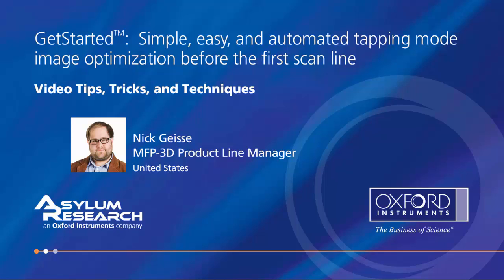Today, I'm going to talk to you about a new feature for Asylum Cypher and MFP 3D Infinity atomic force microscopes called GetStarted. GetStarted makes your AC mode imaging in air easy by calculating the gain, drive amplitude, set point, and scan rate for you. That's right, GetStarted optimizes your initial scan parameters and gets you imaging quickly and efficiently. Best of all, GetStarted does all of this before you even touch the surface, reducing the chances of damage to your tip and sample.